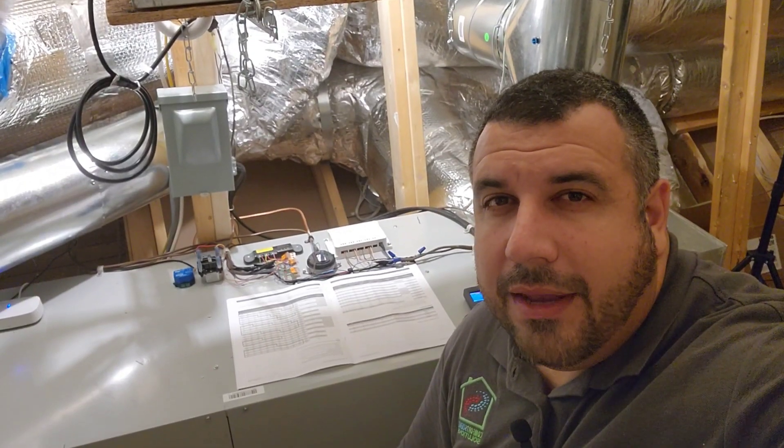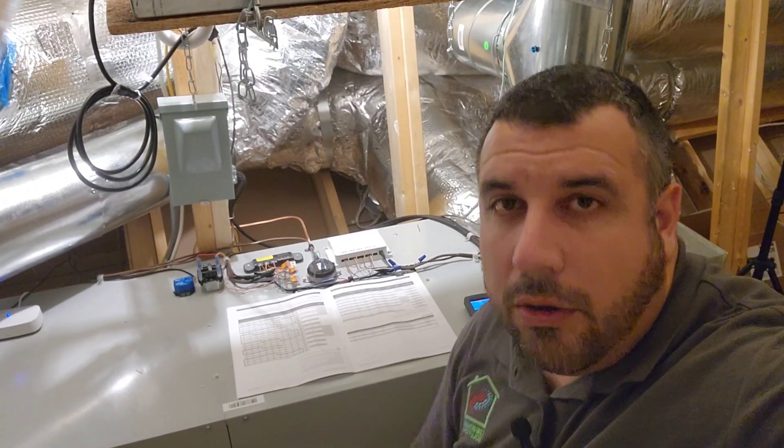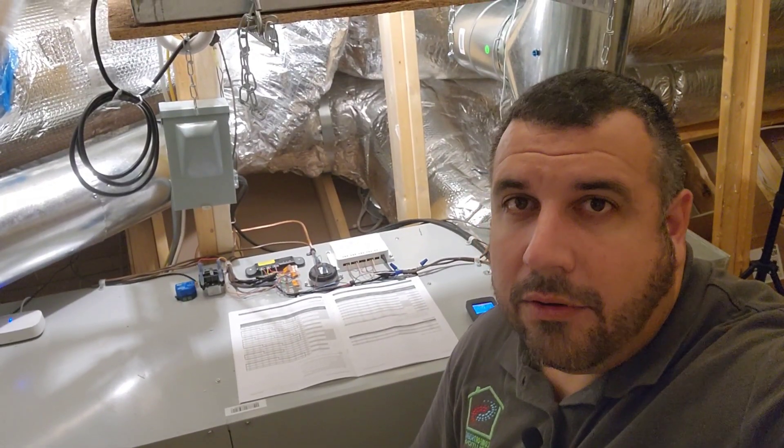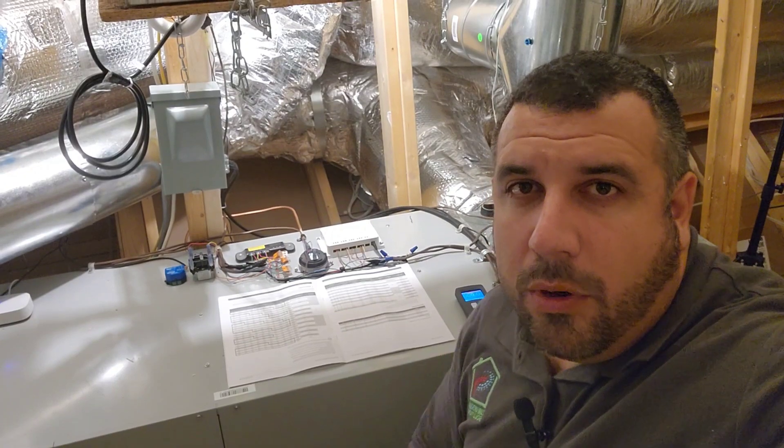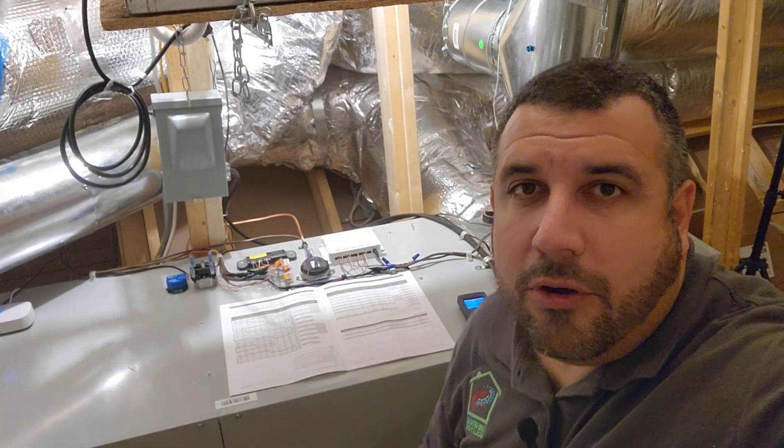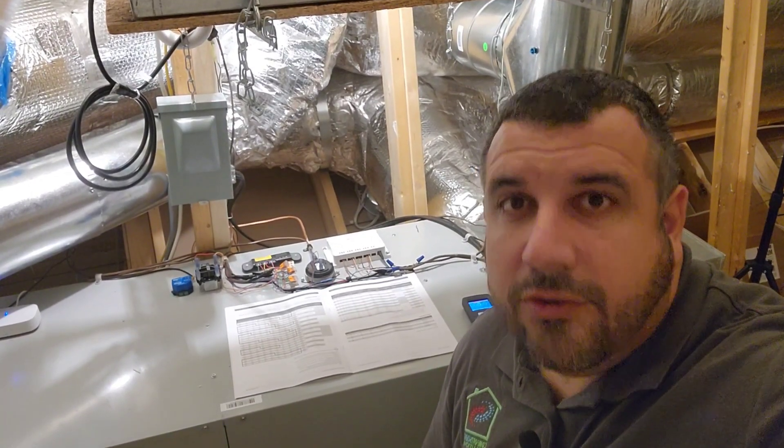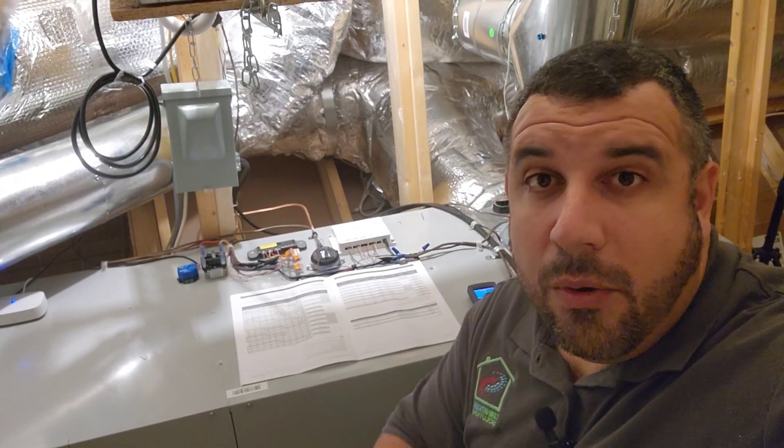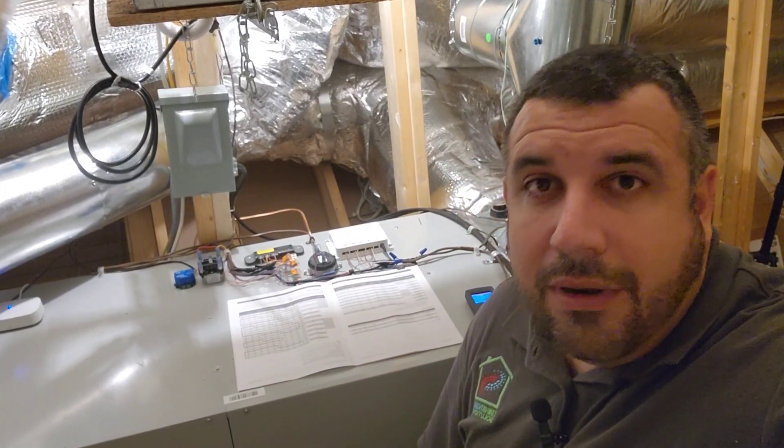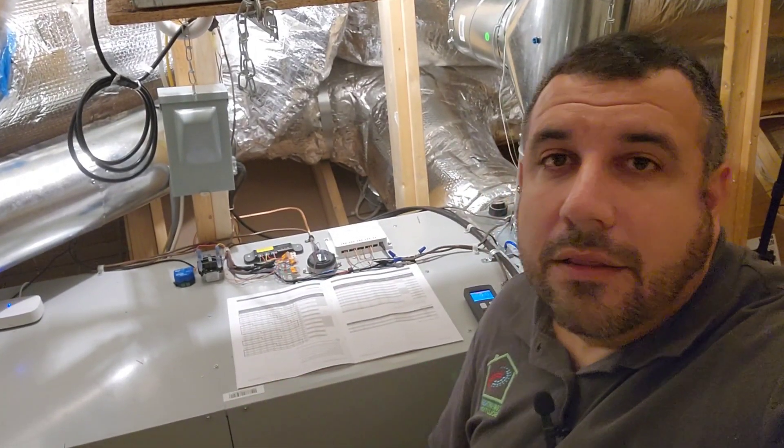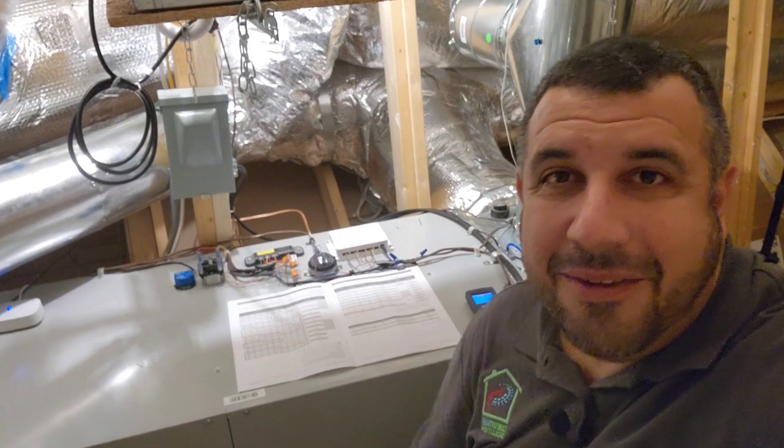The thing about airflow is that it's one of the most important things to test and use in diagnosis, but it's also one of the hardest things to do so accurately. And a static pressure check is the very basic way of checking airflow. We're going to use static pressure, compare it against the blower chart that comes from the manufacturer. Now, that is not a perfect test. There are some limitations, and we're going to go over that in the video. But for now, we're going to show you, as a service technician, how you can take a fairly accurate airflow reading from your air handler just using static pressure and the blower chart. So if you've never done that before, stick around, I'll show you how.